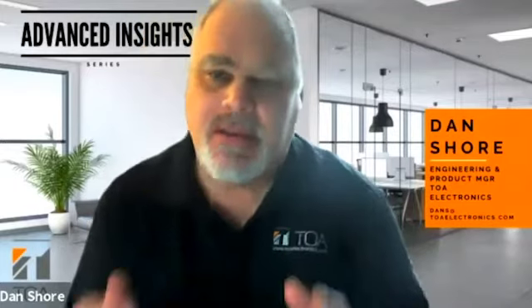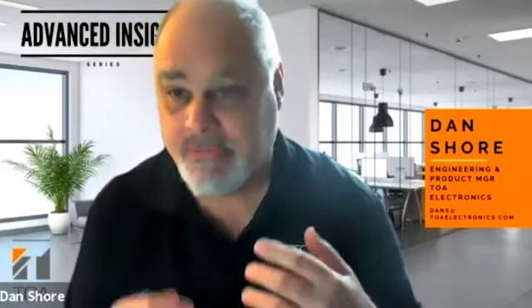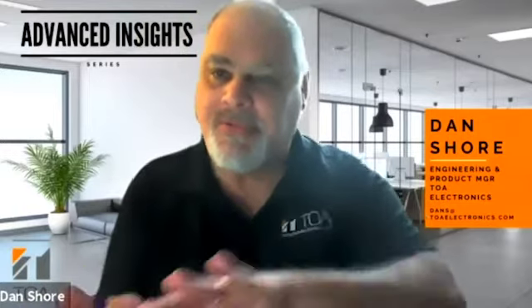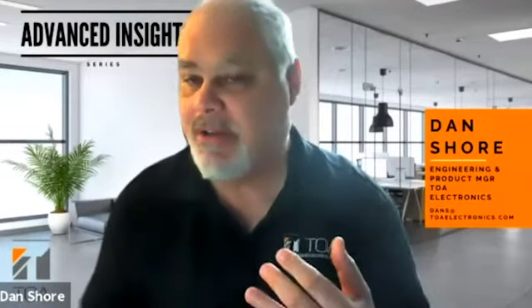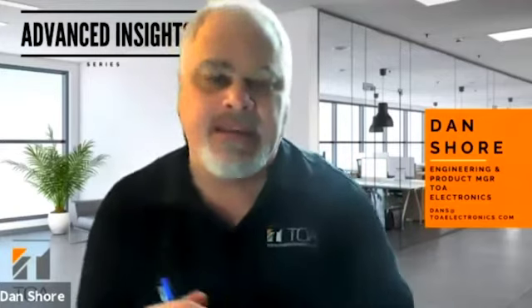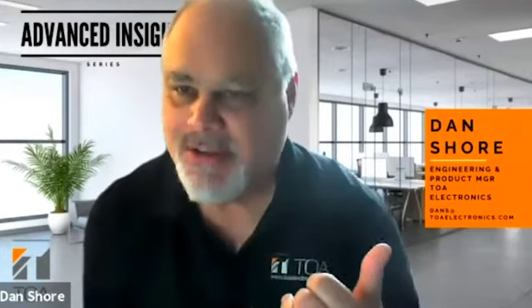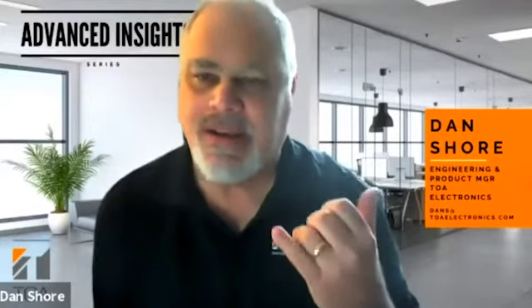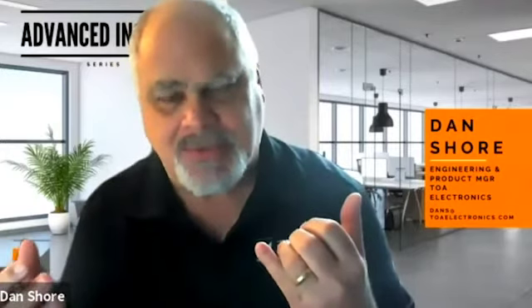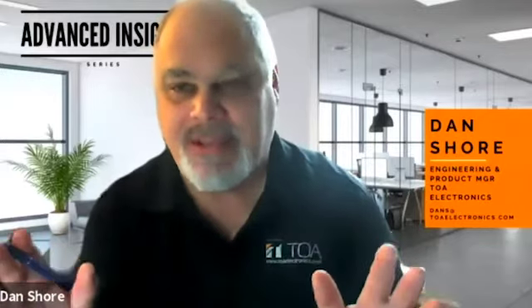phone system. An emergency system relies on a limited number of inputs to the system for the emergency purposes. We expand off of that to get our general paging and music systems. So folks that want to have a phone system used as an emergency communication system, we try and discourage them from that because if you've dealt with SIP systems before, the server will go out, you'll have to reboot your phone, you can't have that in an emergency.